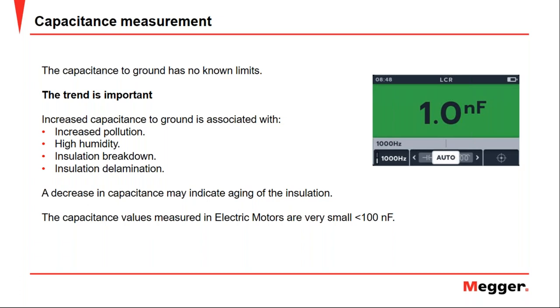Capacitance. As we said before, capacitance is useful, like inductance, only by trend. That is why we must take several measurements before carrying out any kind of analysis. Now, let's see what we can know with the capacitance test. We have two scenarios. If we detect an increase in the capacitance to ground, this is associated with increased pollution, high humidity, insulation breakdown, or insulation delamination. But on the other hand, a decrease in the capacitance to ground may indicate aging of the insulation.